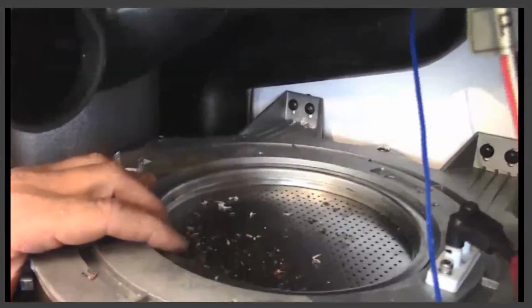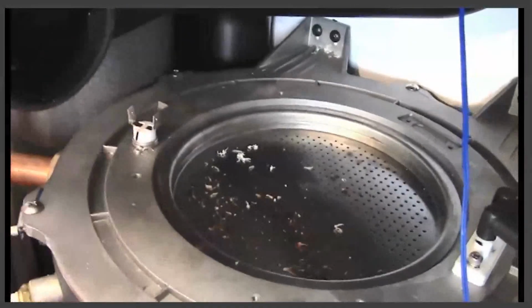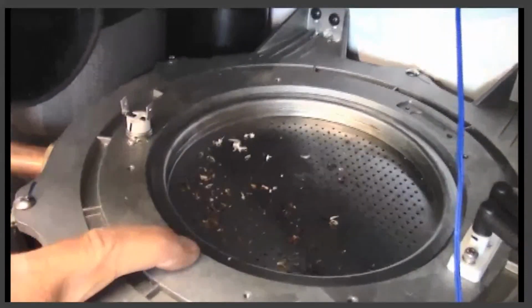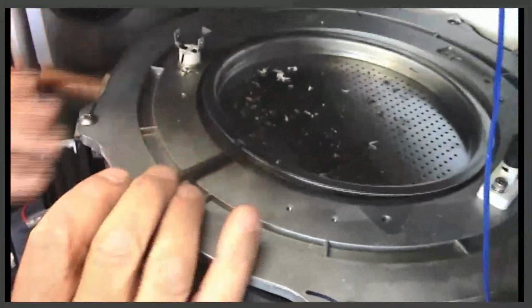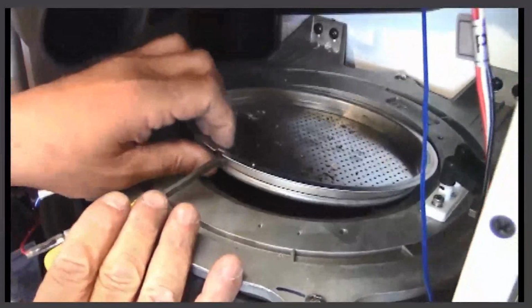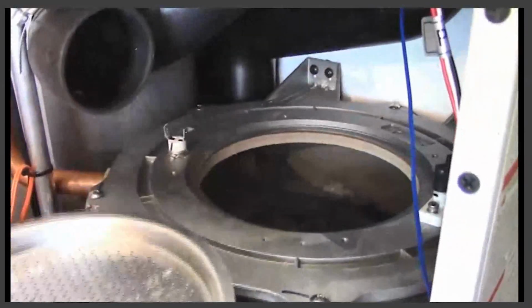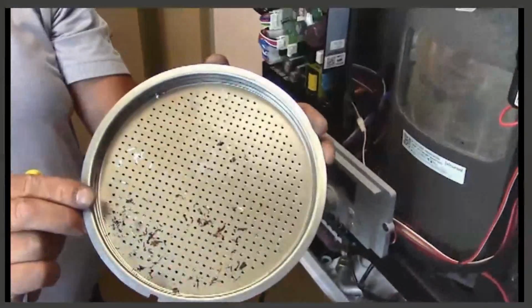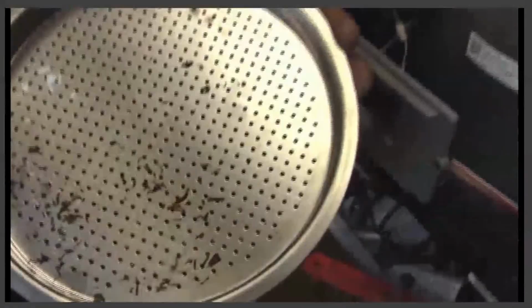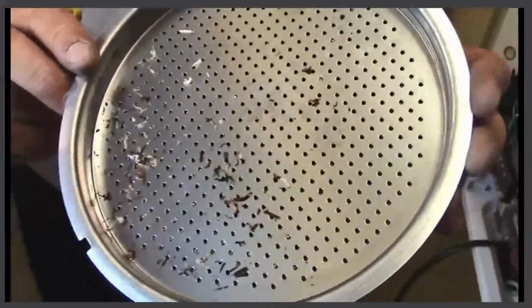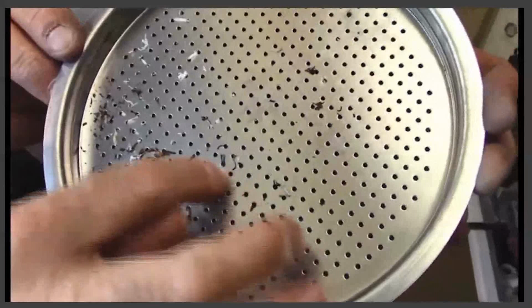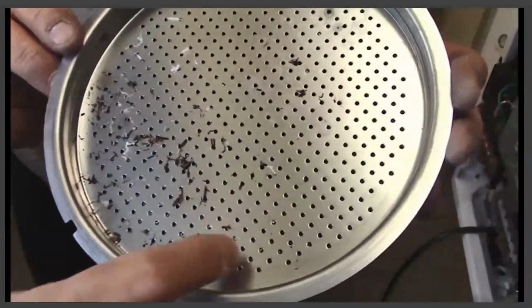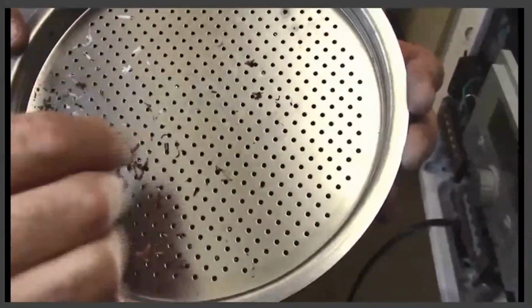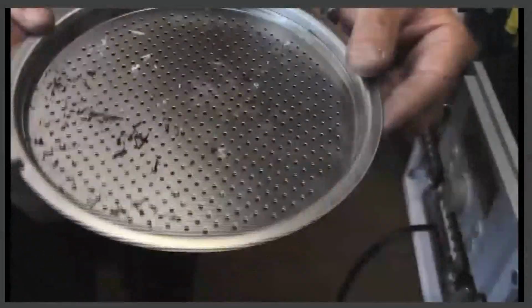Removal of the burner plate is best done with a small screwdriver. You'll notice that there is a notch in the very front of that burner plate. Insertion of the screwdriver into that notch, and you can lift the burner plate out of position from the top of the boiler. Here you're seeing those PVC shavings that Steve mentioned earlier. So here are some that are not burnt off, and here are some that started to melt and burn off. And what happens is they will actually plug these orifice holes, and you won't get proper firing.